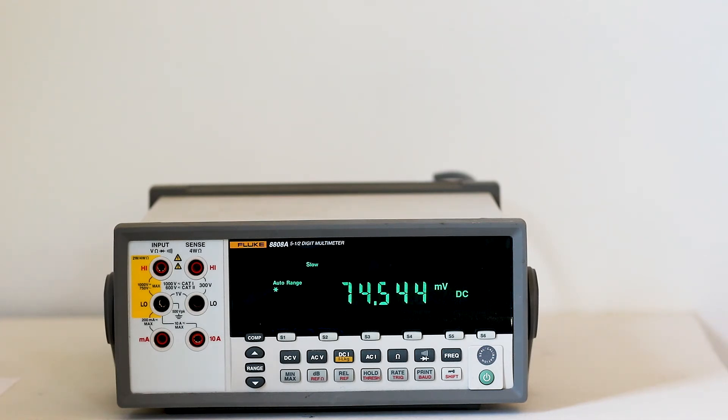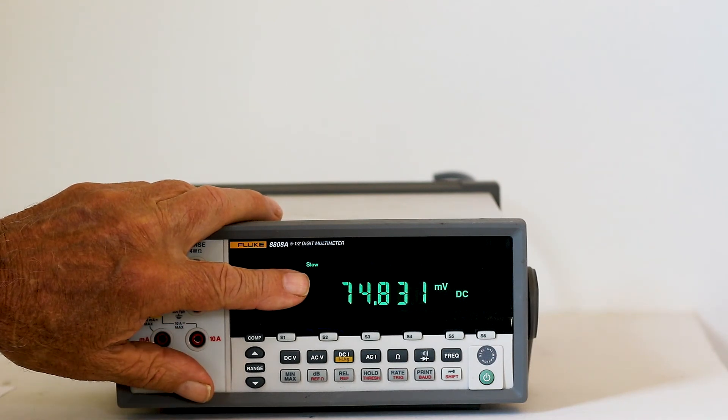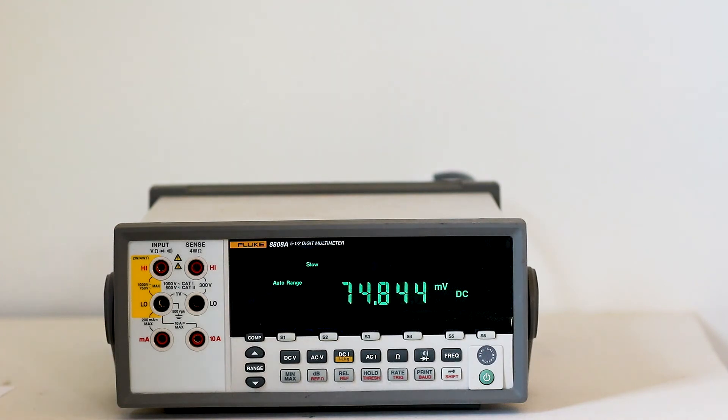Built-in TrendPlot graphically plots extent of drift and intermittent events. The histogram mode can reveal stability and noise problems. If you can see the fluctuating numbers in the readout, that is phantom voltage, as in any digital voltmeter. Auto range makes the meter so sensitive that it reads its own internal noise floor.